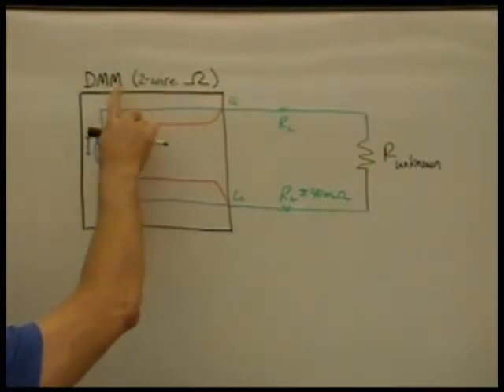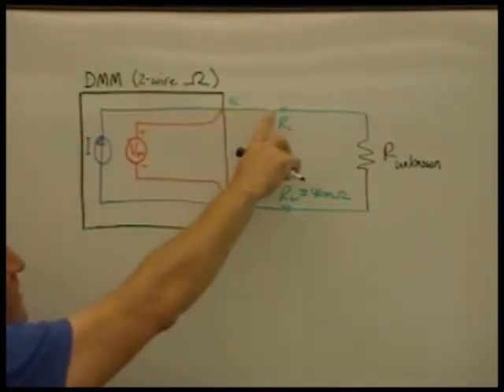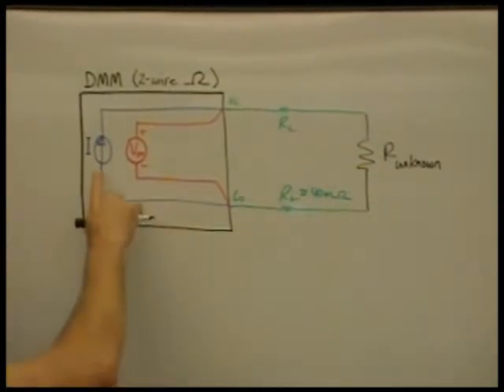Inside the DMM, we have a current source. This is a constant current source. We actually have many of these depending upon what resistance range you're using. So we output a known current through the high terminal, our unknown resistance, and back through the low terminal.